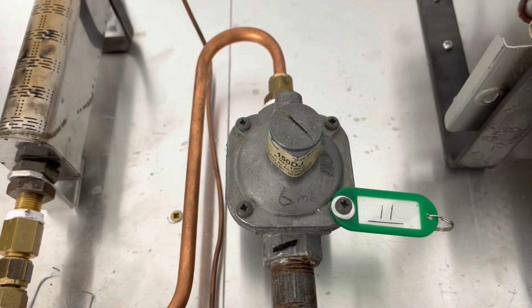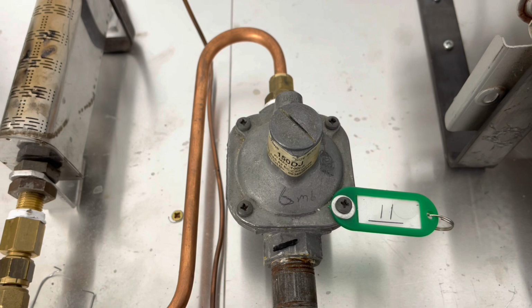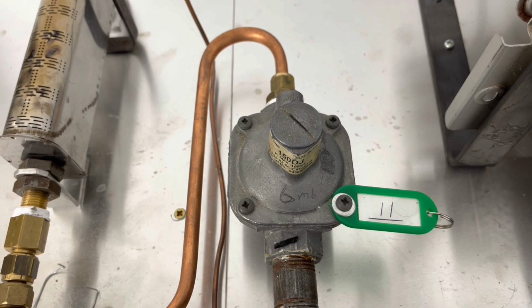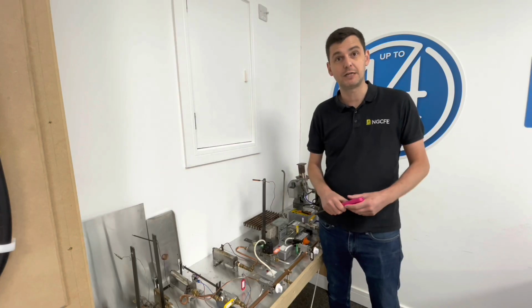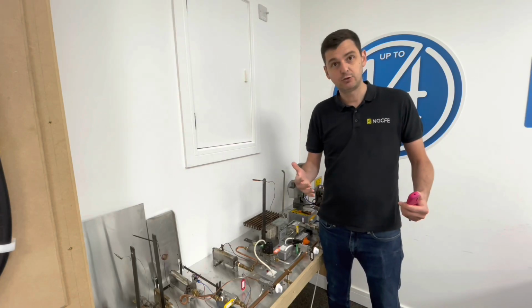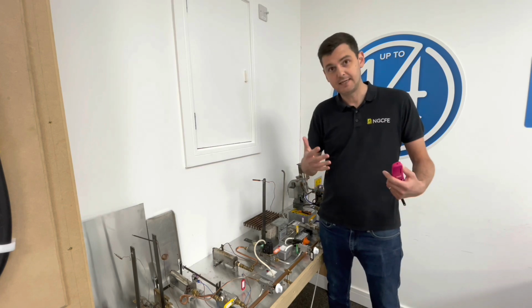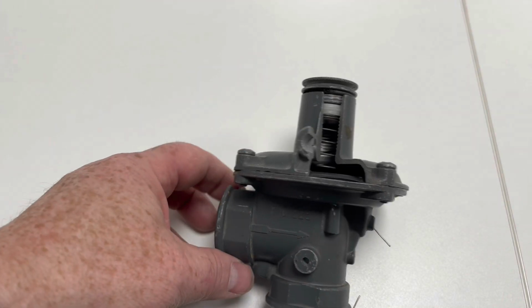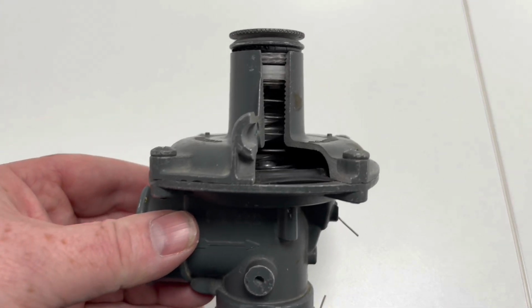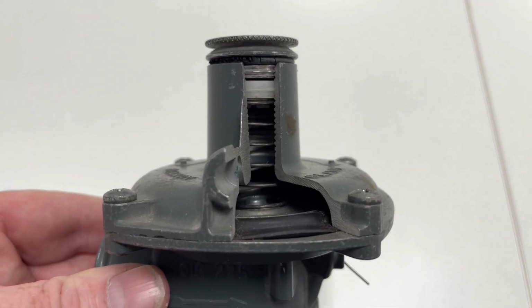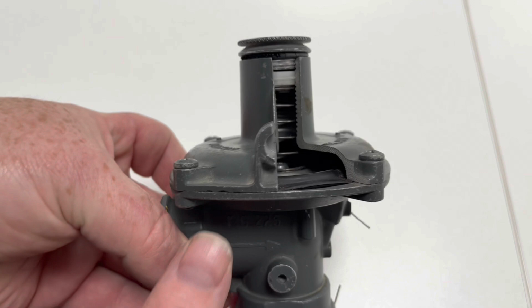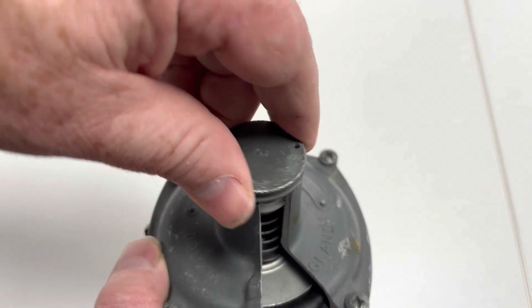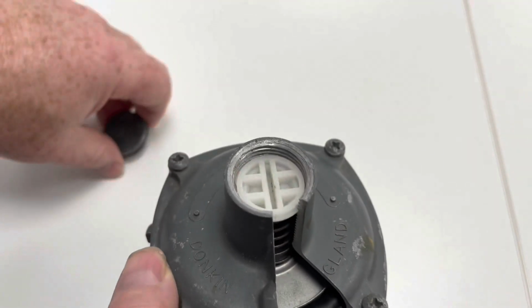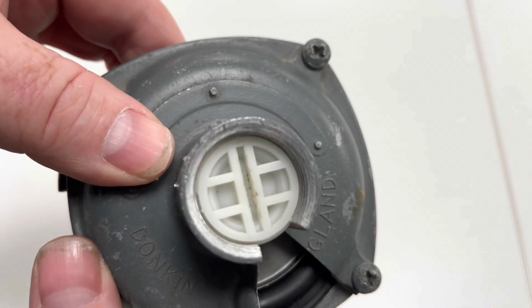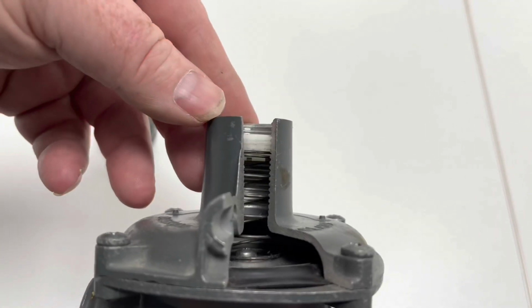We've also got a low pressure regulator. Now, a low pressure regulator, although this one looks slightly different, it's exactly the same type of regulator that you see on your gas meters. All the regulator does, or a governor, is it maintains a constant outlet pressure on a gas valve, and it does this via a diaphragm. So when the gas goes through the valve, depending on what the outlet pressure is, or what the system is drawn off from the regulator, the diaphragm will alter to maintain a constant outlet pressure.